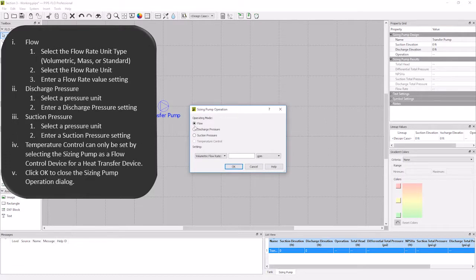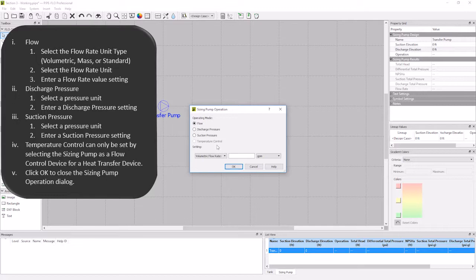Flow rate, discharge pressure, and suction pressure. There's also temperature control, but this can only be used when we are talking about the heat source sink device. For my system, I'm going to specify the flow rate. I need 800 GPM, so I will enter 800 for my GPM.